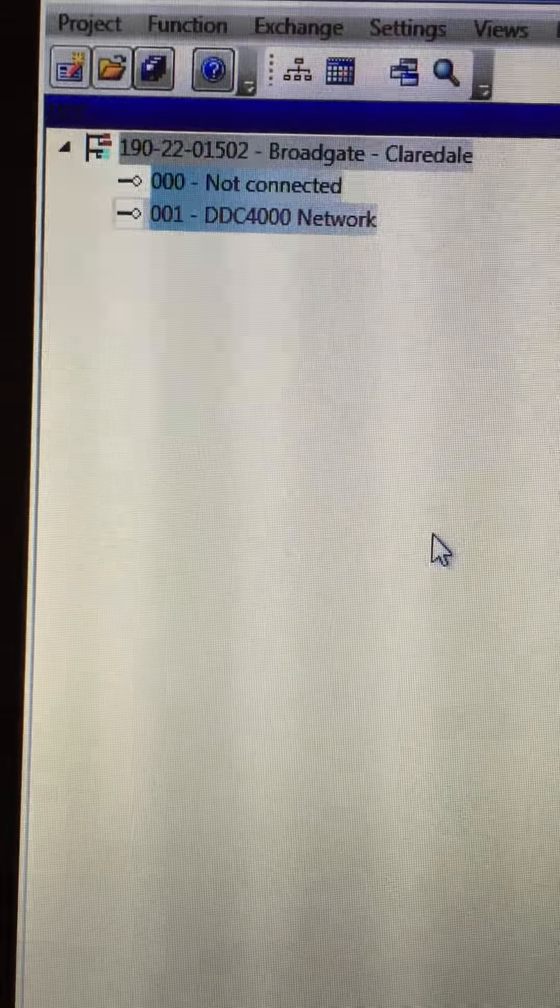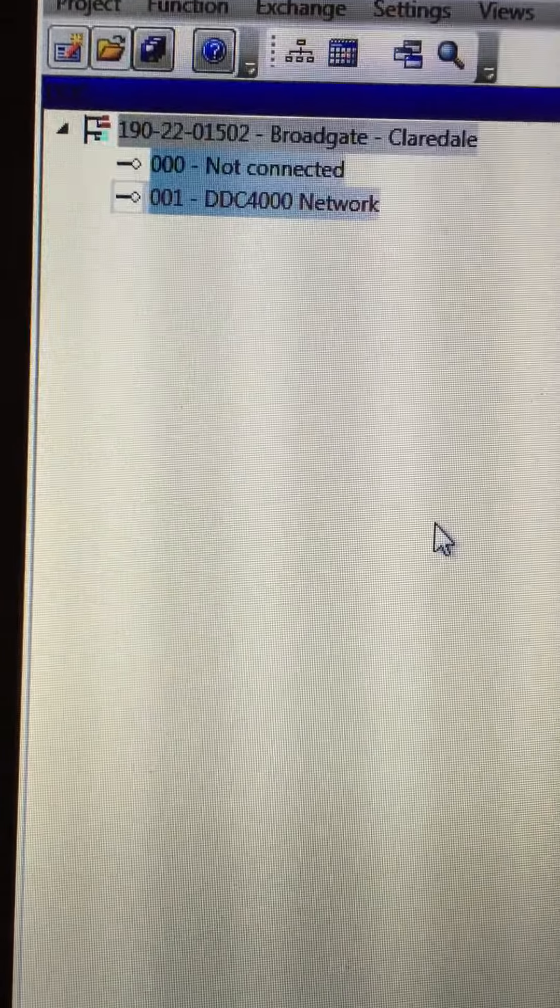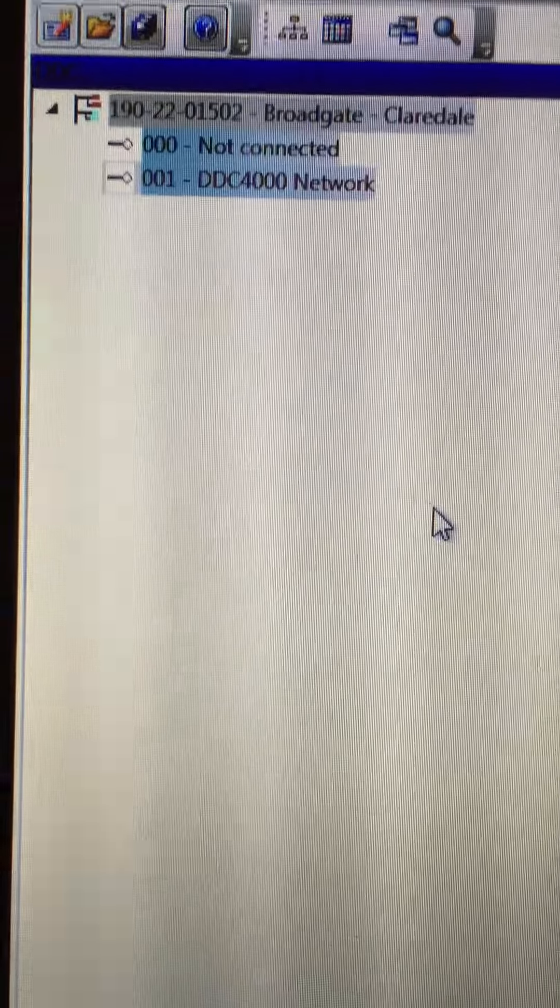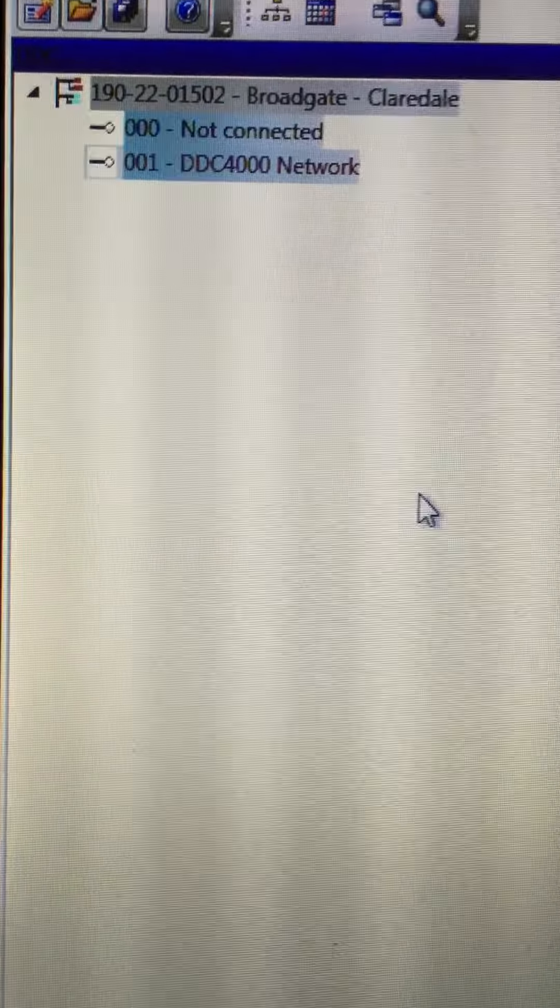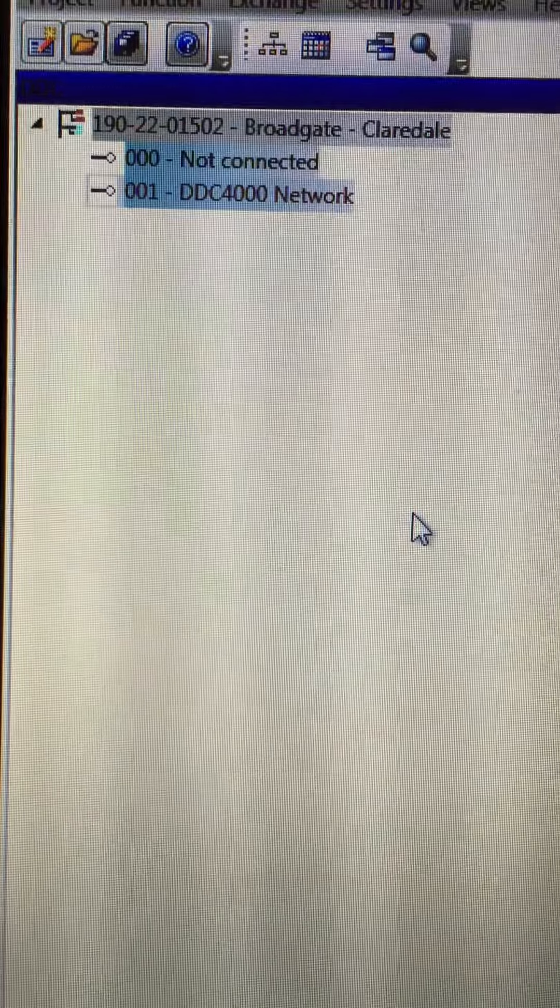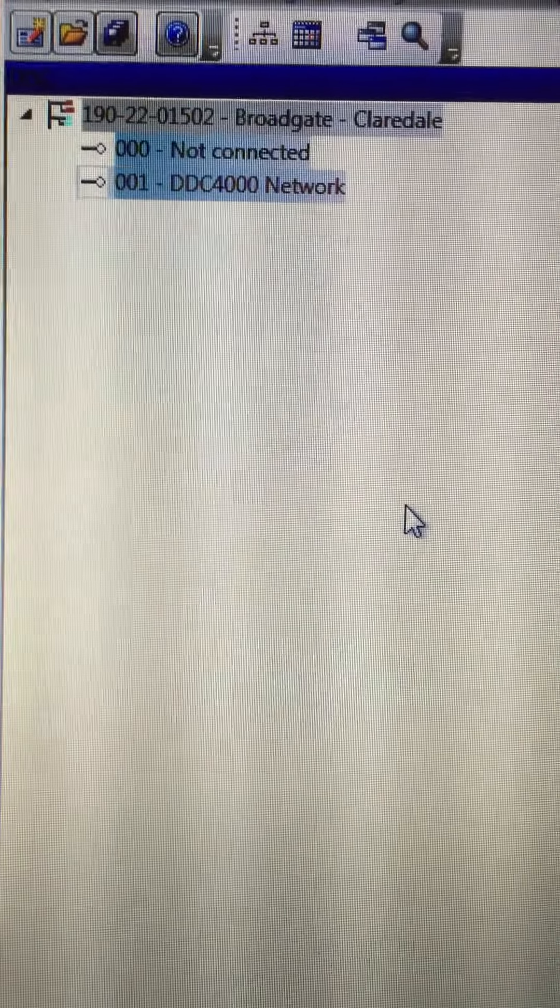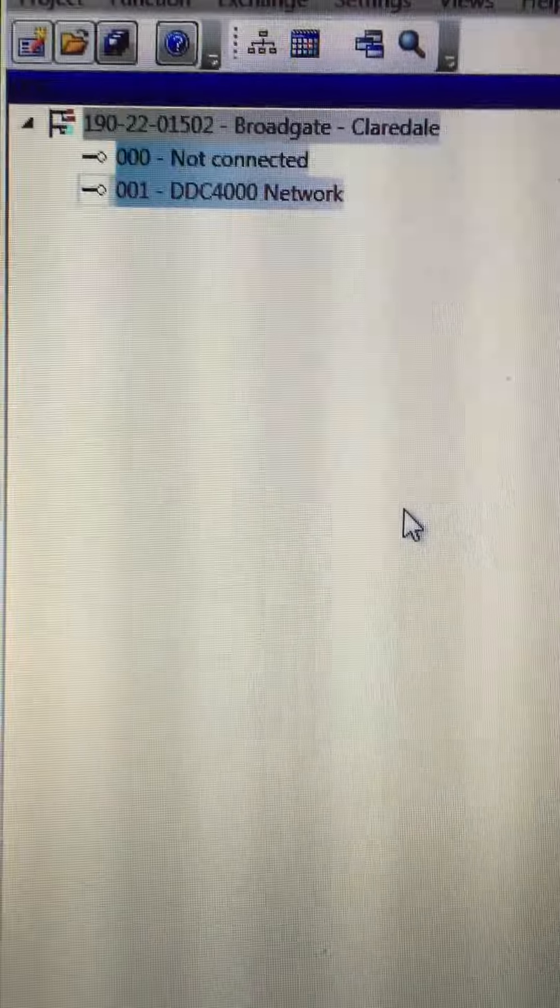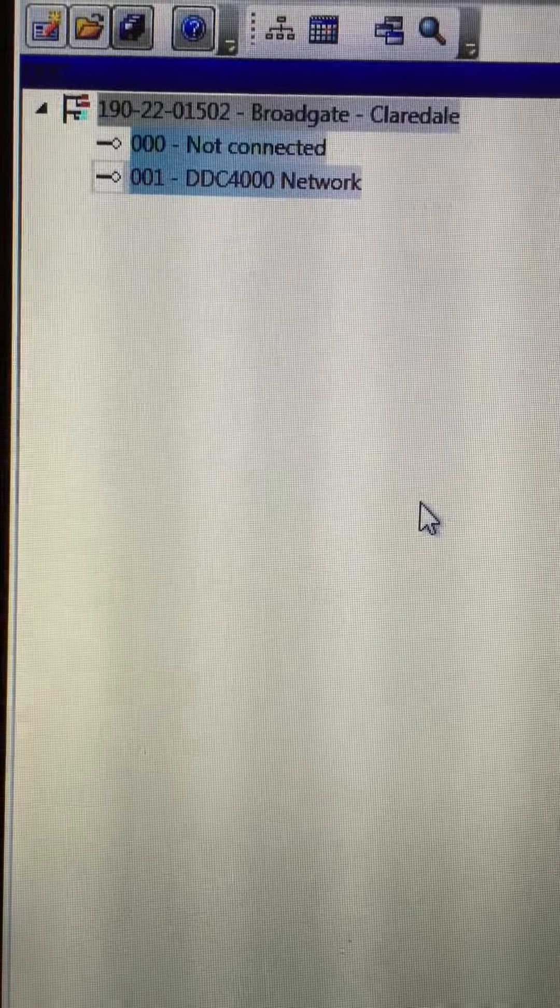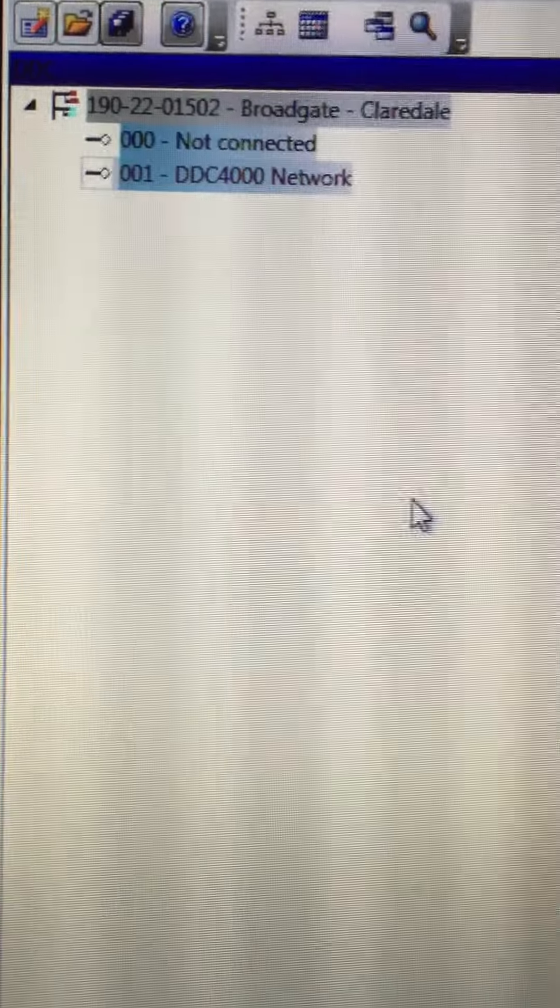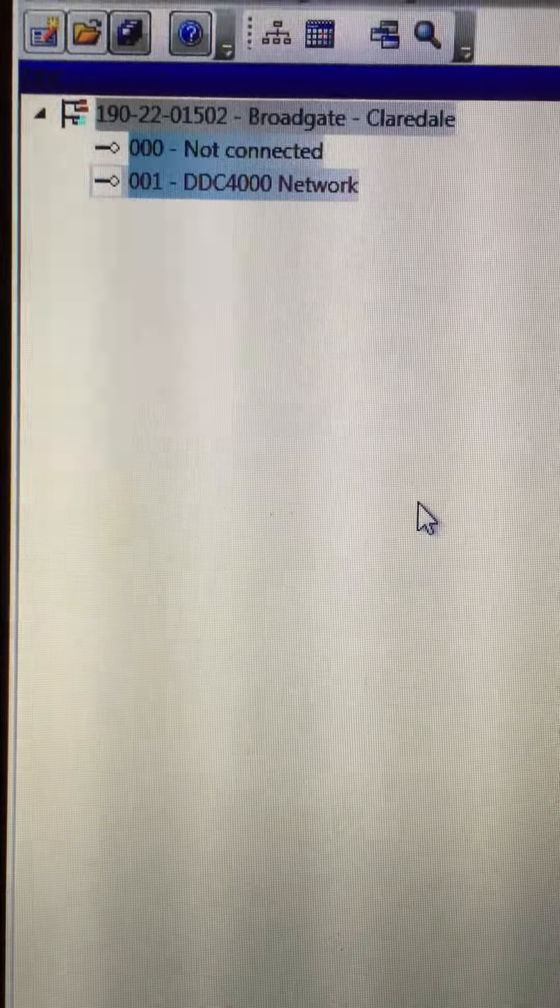Hello, it's a video just showing how to set up and configure a DDC4000 controller inside PS4000 so that you can get a direct download into the controller physically. I showed an earlier video how to commission the controller to give it an IP address and a default ID. You have to apply the same settings inside PS4000 so that the two can communicate.